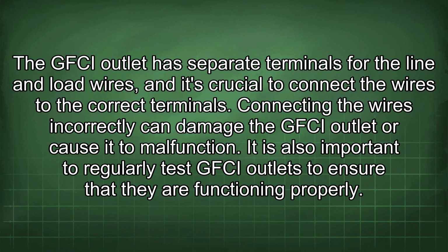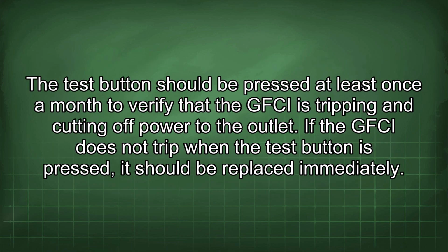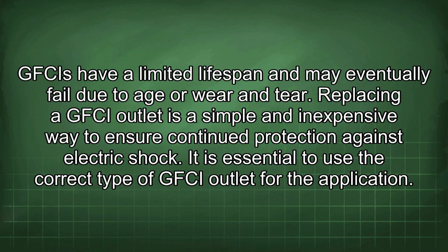It is also important to regularly test GFCI outlets to ensure that they are functioning properly. The test button should be pressed at least once a month to verify that the GFCI is tripping and cutting off power to the outlet. If the GFCI does not trip when the test button is pressed, it should be replaced immediately. GFCIs have a limited lifespan and may eventually fail due to age or wear and tear. Replacing a GFCI outlet is a simple and inexpensive way to ensure continued protection against electric shock.